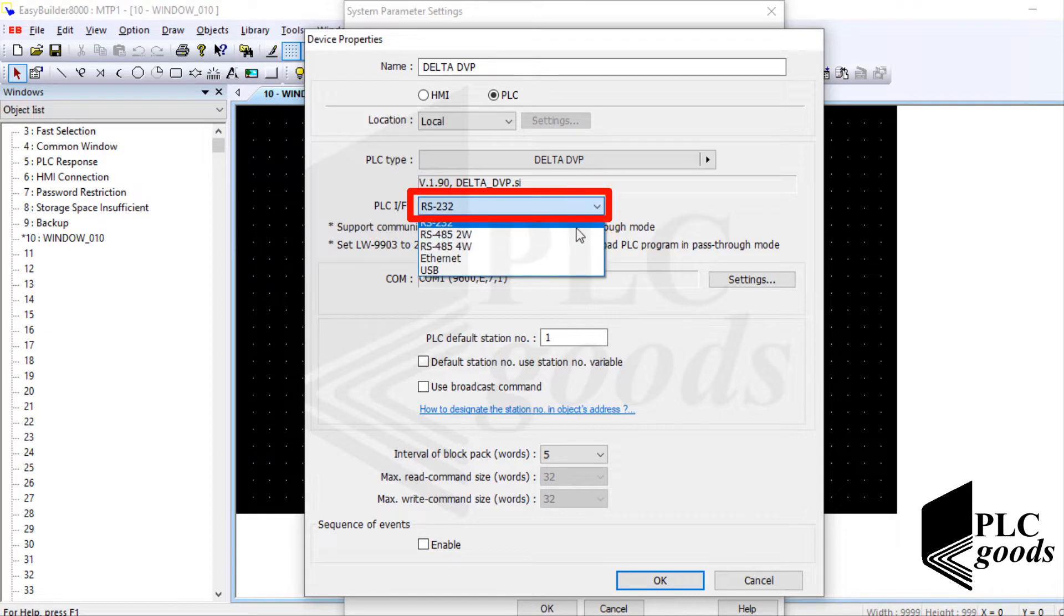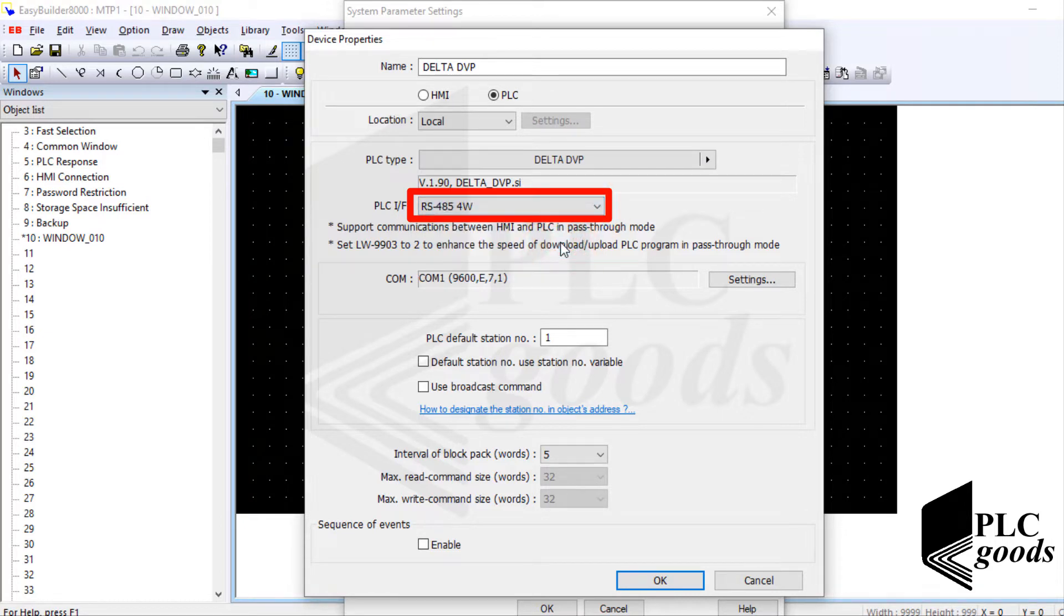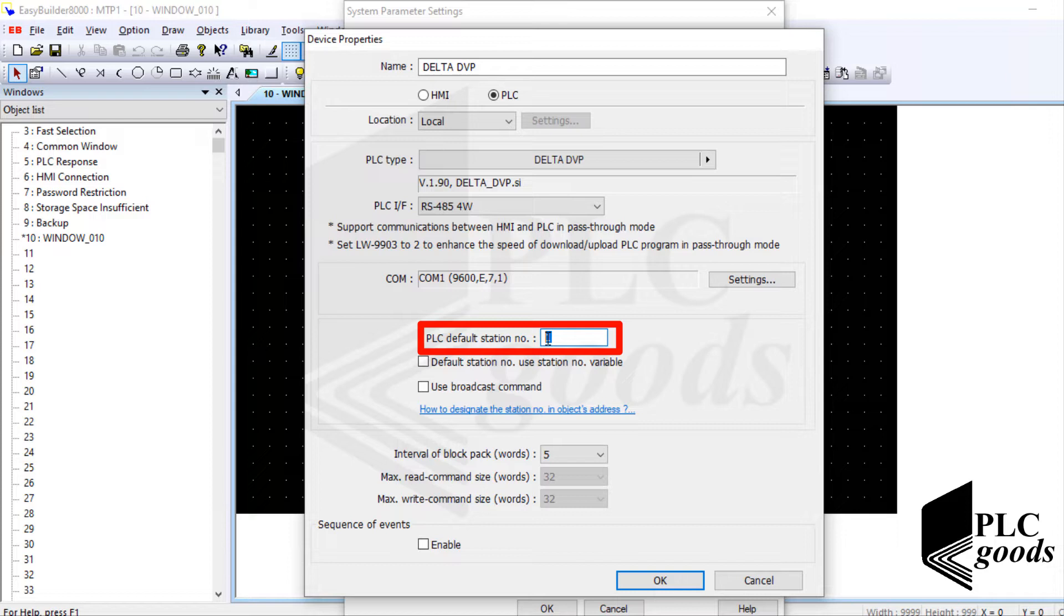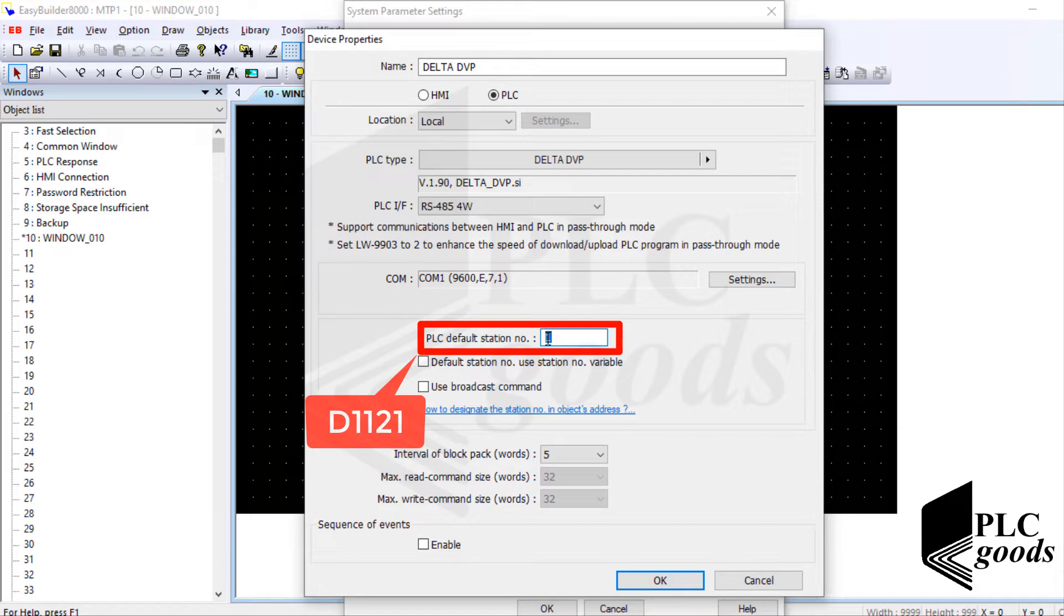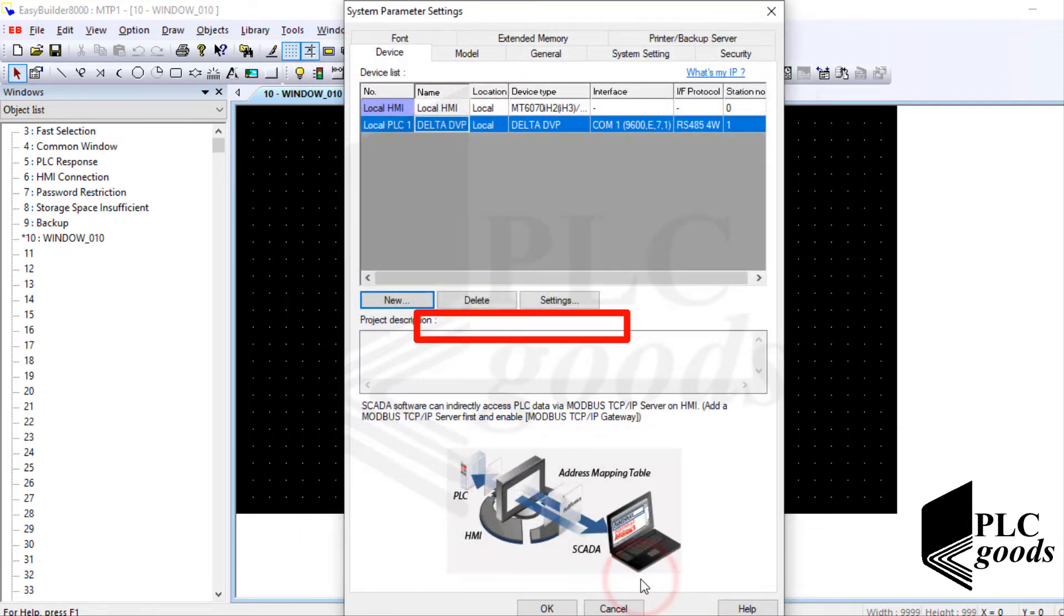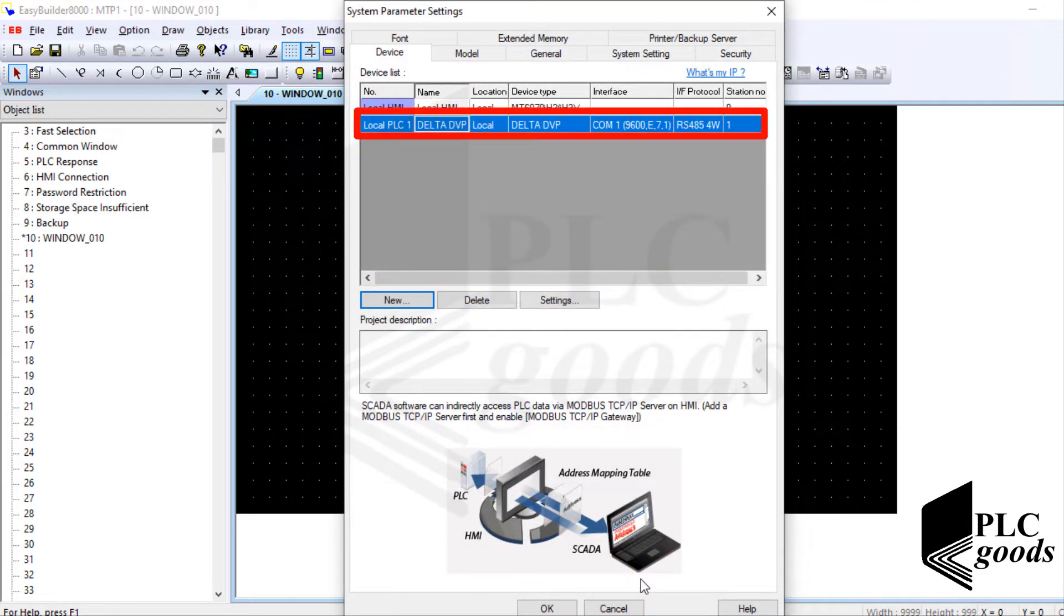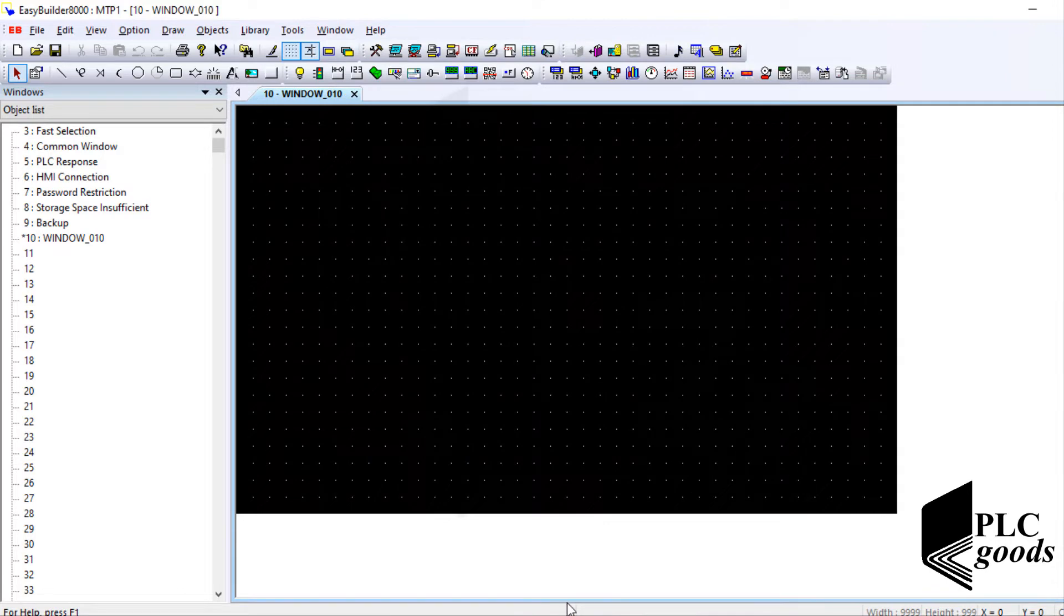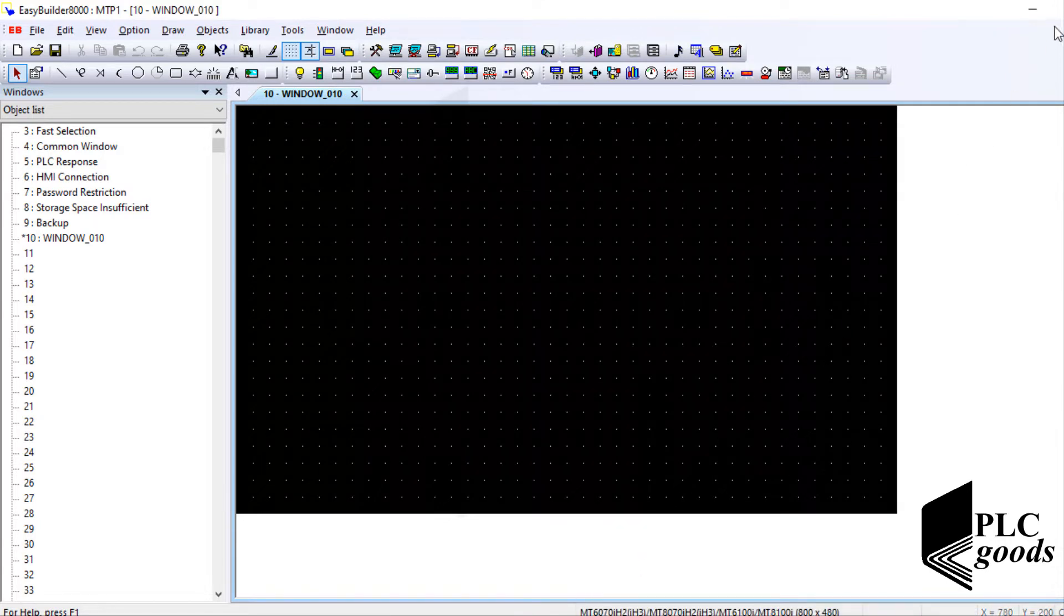Another important parameter is the PLC station number. Note that if multiple PLCs are connected to the same network, each PLC must have its own unique number. By default my PLC station number is 1 but it can be changed by D1121. All right, the new connection has been created. Now I can use my PLC data inside the HMI. Let's continue to design a simple HMI screen.